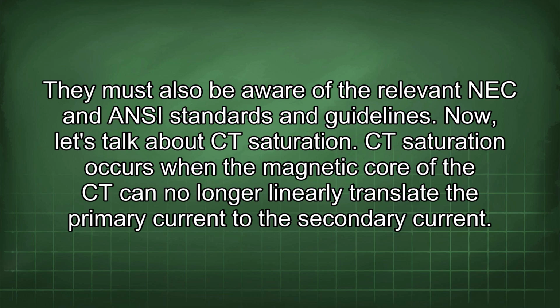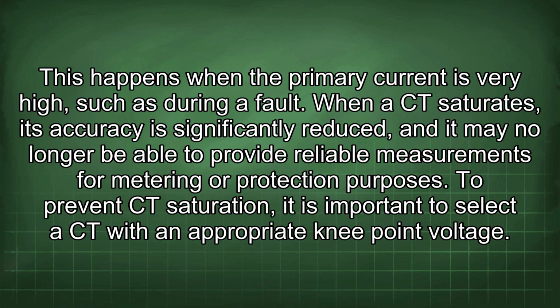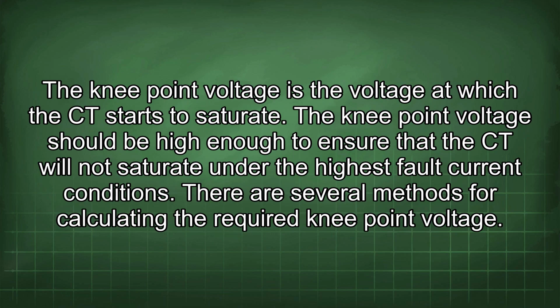CT saturation occurs when the magnetic core of the CT can no longer linearly translate the primary current to the secondary current. This happens when the primary current is very high, such as during a fault. When a CT saturates, its accuracy is significantly reduced, and it may no longer be able to provide reliable measurements for metering or protection purposes. To prevent CT saturation, it is important to select a CT with an appropriate knee point voltage. The knee point voltage is the voltage at which the CT starts to saturate. The knee point voltage should be high enough to ensure that the CT will not saturate under the highest fault current conditions.